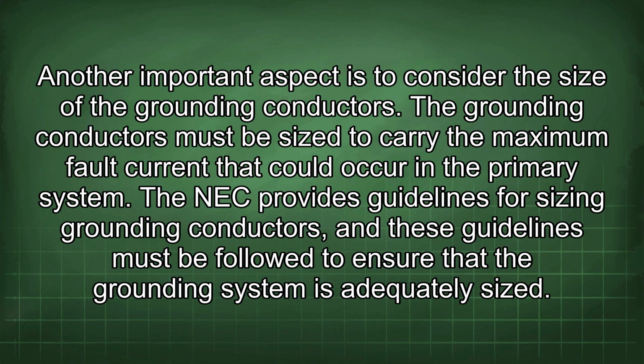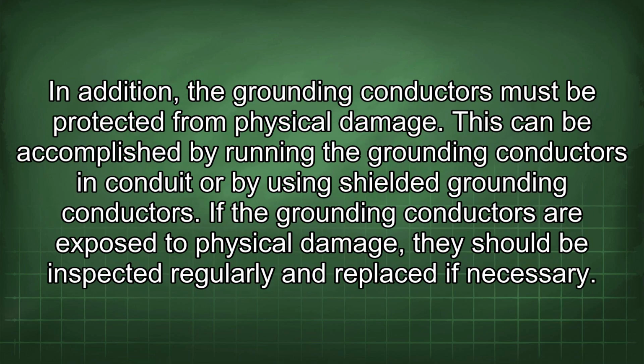In addition, the grounding conductors must be protected from physical damage. This can be accomplished by running the grounding conductors in conduit or by using shielded grounding conductors. If the grounding conductors are exposed to physical damage, they should be inspected regularly and replaced if necessary.